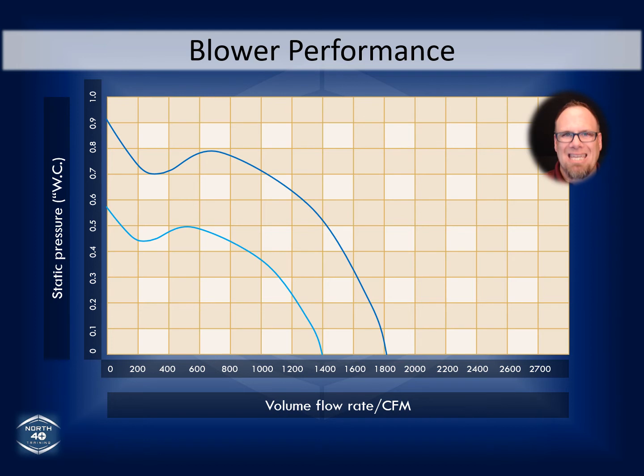These systems get their maximum efficiency by allowing the most amount of airflow to go through there, so they move the most amount of air while having it at the right temperature when they're doing it. That helps dehumidify and cool in the summer and heat in the wintertime, but it also, on a larger scope, over the long haul of this system's life, it will preserve that life. It won't be working as hard. It won't sweat in places it's not supposed to sweat. It won't have problems that go unseen for years and years that will eventually lead to large, expensive problems. So blower performance is a huge, huge factor in everything that we do.